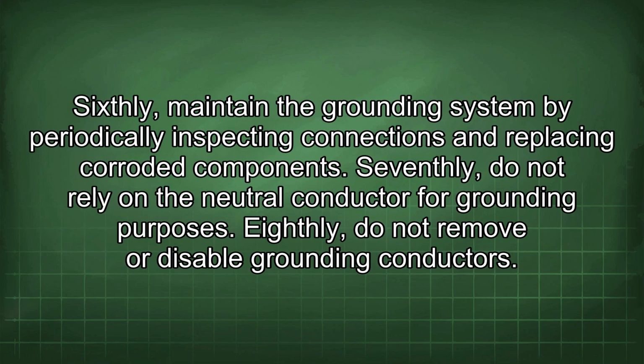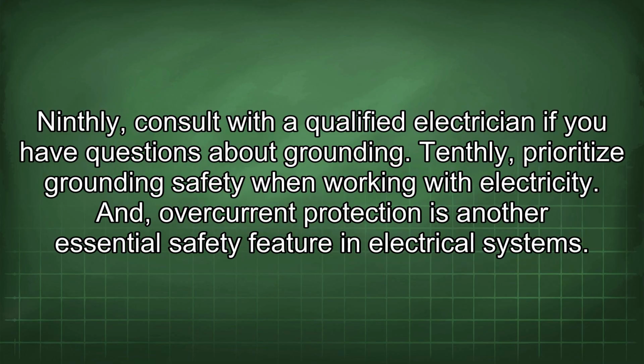Sixthly, maintain the grounding system by periodically inspecting connections and replacing corroded components. Seventhly, do not rely on the neutral conductor for grounding purposes. Eighthly, do not remove or disable grounding conductors. Ninthly, consult with a qualified electrician if you have questions about grounding. Tenthly, prioritize grounding safety when working with electricity.